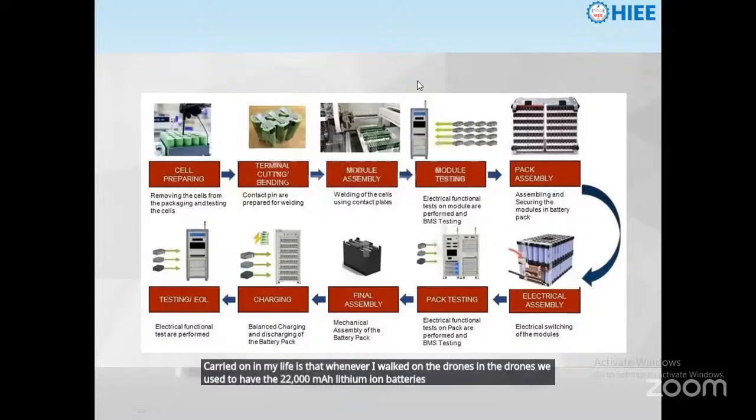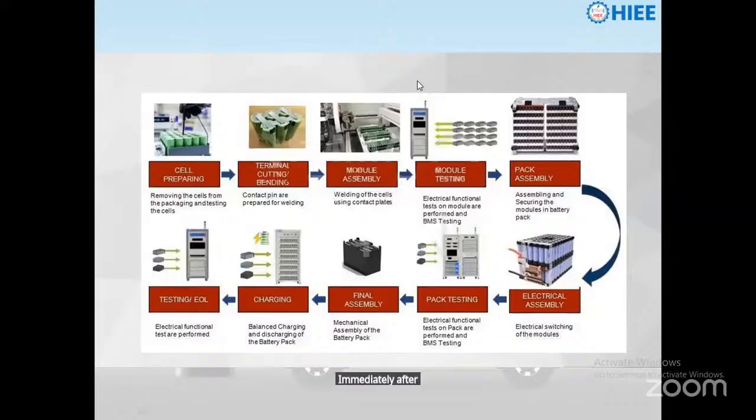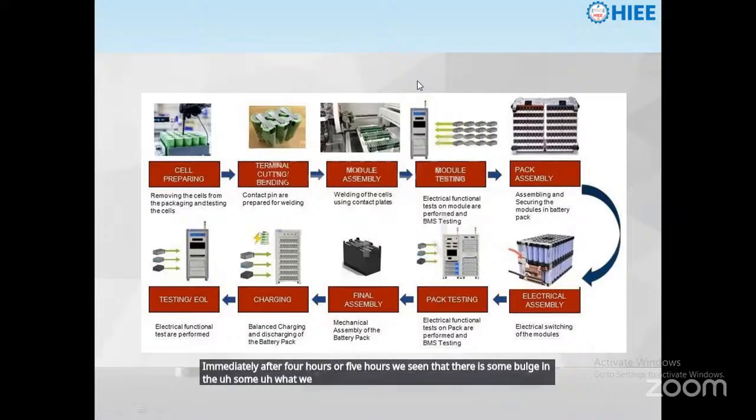Okay, so in one case with our team, we bought a new lithium ion battery. That lithium ion battery fell down from 3 feet of height. Immediately after 4 or 5 hours, we saw that there was some bulge in the shape of that battery.